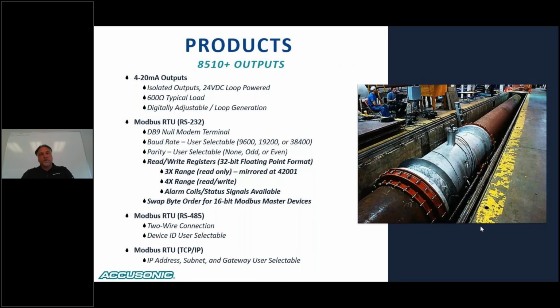Specific to Modbus 485, it is a 2-wire connection, and the device ID is selectable on the touchscreen display, anything from 1 to 255. And for TCP/IP, the really only difference there is that the IP address, the subnet, and gateway have to be programmed into the flow meter to communicate with the Modbus master in the TCP/IP realm.